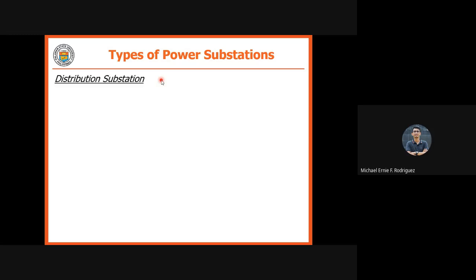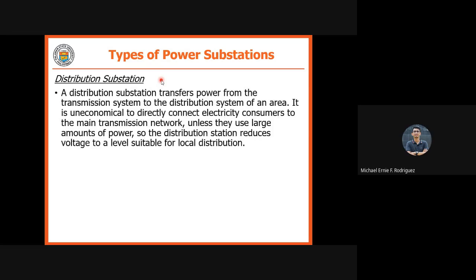And I think this is the last type, distribution substation. Ito na yun nandyan sa Paleco substation. So that transfers power from the transmission system to the distribution system of an area. So, ito naman kapag it is uneconomical to directly connect electricity consumers to the main transmission network unless they use large amounts of power. In the case ng ating mga industrial, di ba? Meron kang customer substation, directly connected to your main transmission system or to a transmission system or sub-transmission system. So, the distribution station reduces voltage to a level suitable for local distribution. For example, 13.2 kV or 34.5 kV in the case of Meralco system.